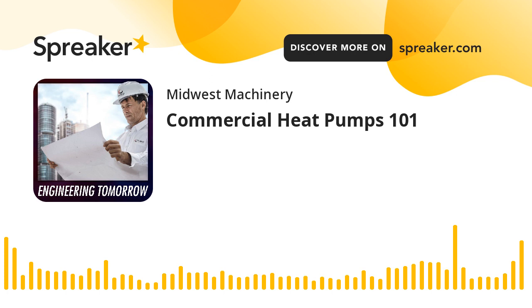Okay, Jeff, let's say we decide we want to go with a heat pump, or we're in the preliminary stages. How are you going to size your job and your equipment? So it's different. Everybody kind of has their own way of doing it. When I'm working on a project, what we tend to suggest is you first do your zone checksums for each individual zone to figure out what size heat pump you need. You might find out one room needs a 1-ton unit, another room needs a 1.5-ton unit, and so on.